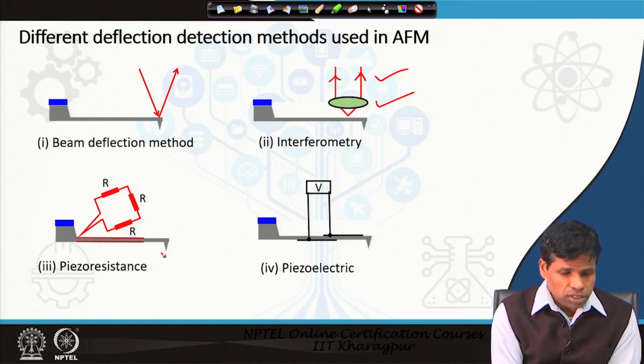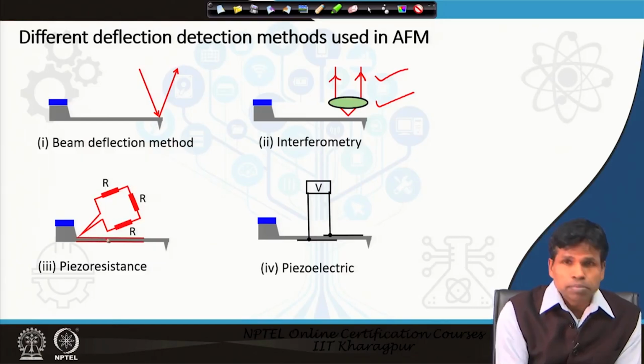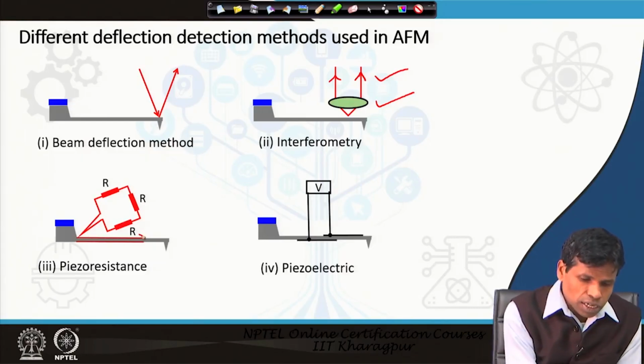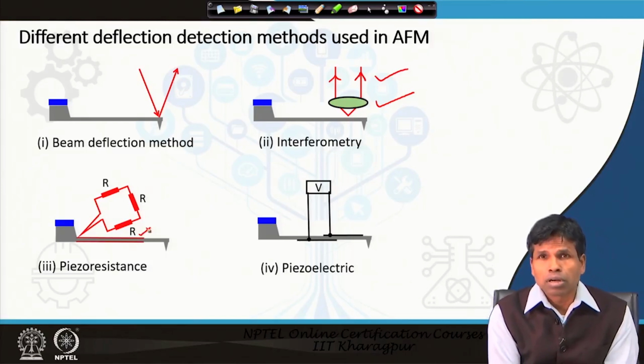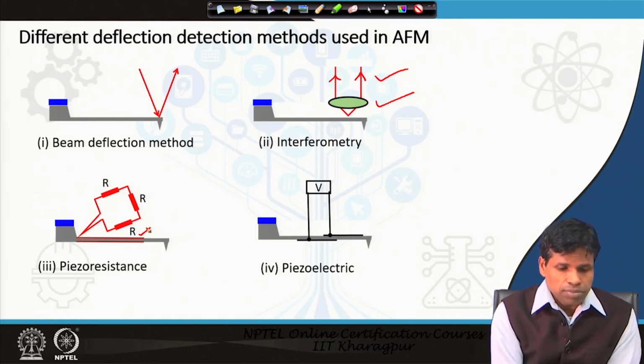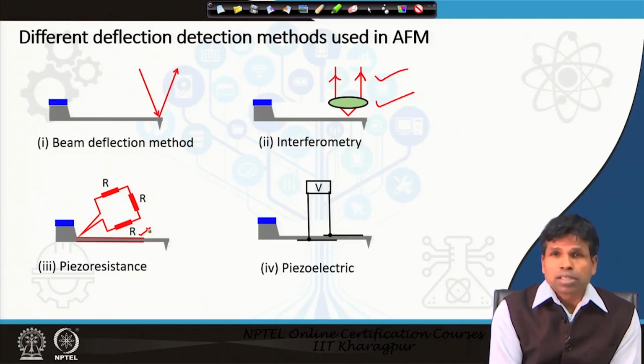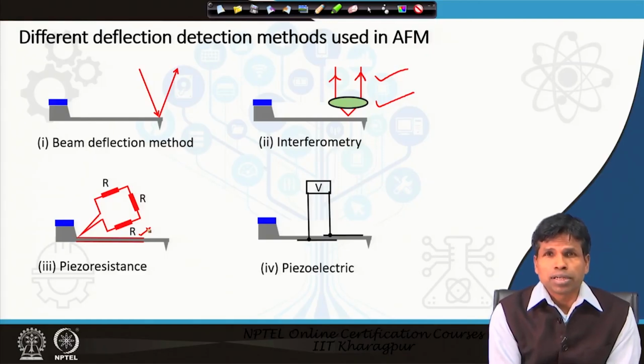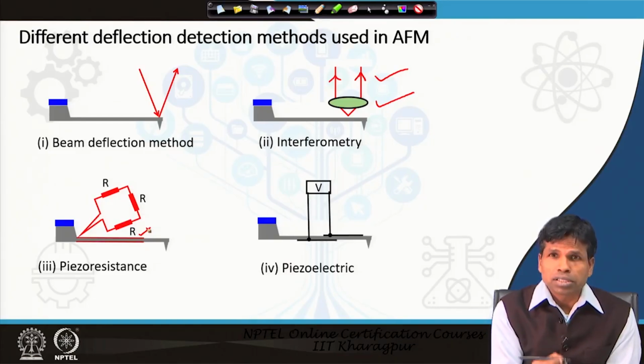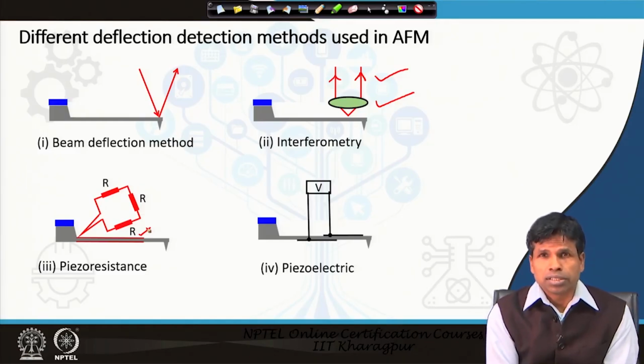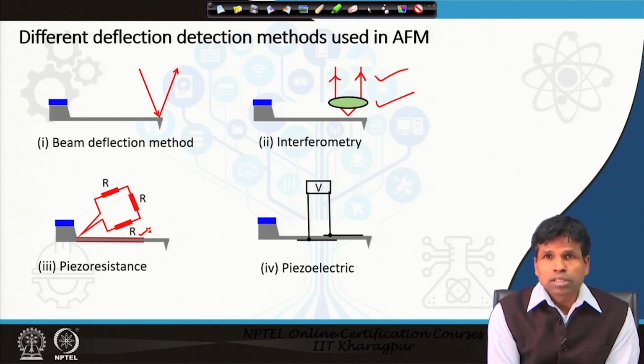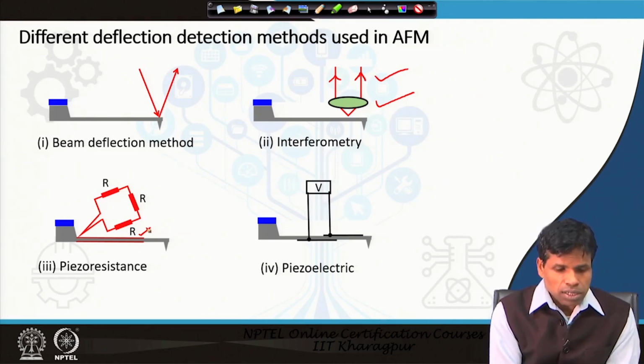In the piezoresistive detection method, a piezoresistive layer is coated on the cantilever surface, on the back side of the cantilever, and this piezoresistive layer will change its resistance when mechanical force is applied to the cantilever. So, the resistance of the piezoresistive layer depends on the mechanical stress. Therefore, as the cantilever is deflected upward or downward, there is a mechanical stress on the piezo layer, and thereby a change in the resistance. By measuring the piezoresistance, one can measure how much deflection is occurring.